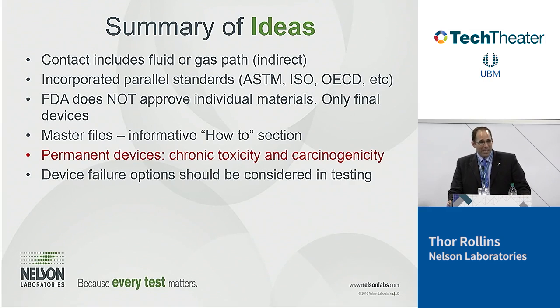That also may be handles, fluid pathways in handles. In the past, when you looked at a handle, it might have a fluid going through it, like some kind of flush channel, and that was not tested because it was in the handle. Now, if you have fluid going through it into the patient, we have to consider that as indirect patient contact. Parallel standards. The FDA actually spells out the parallel standards that they want to follow for certain tests.